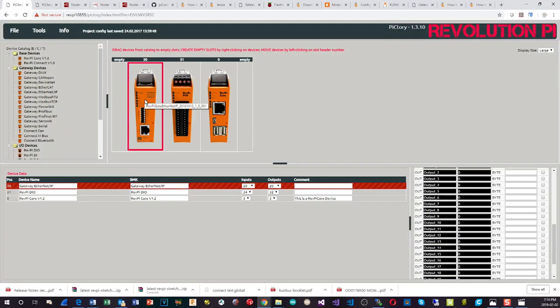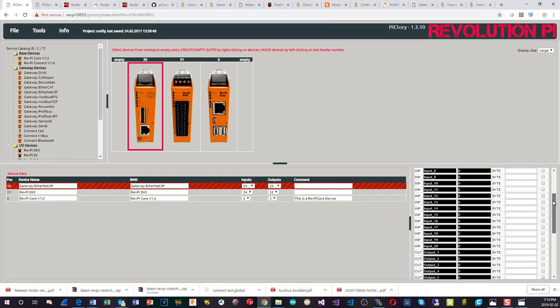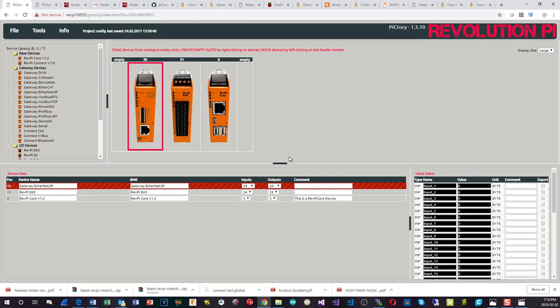The gateway module has similar capabilities. These are effectively memory locations. They're registers as far as a Modbus system is concerned. So they're not binary. They're not bits as you would have for coils. They're just registers. You've got by default 20 in and 20 output. Now you can change this up here. You drop it down. You can have up to 480 for both.